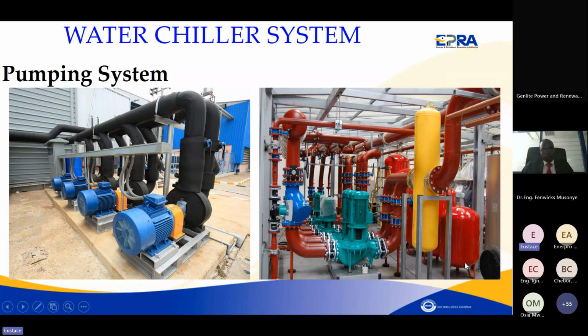Another type of pumping system includes pressure vessels. These are mainly used in areas where you don't want to run the pump throughout, especially when the load is varying. You can use pressure vessels so that when you don't require pumping, the vessel can keep supplying water throughout the system, especially when the load goes down. It's also used to control the pressure within the pumping system. So we can have one without pressure vessels, or one like this with pressure vessels, shown in yellow, which assist in controlling the system and ensure the pump does not run throughout. All these make up the pumping system in a chiller system.